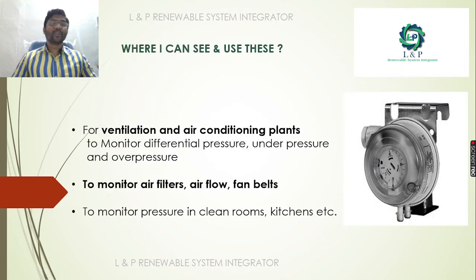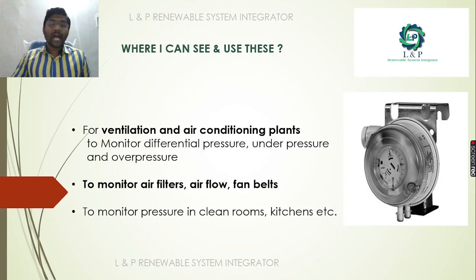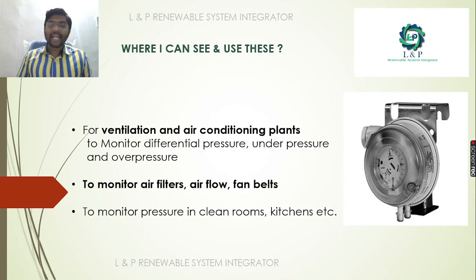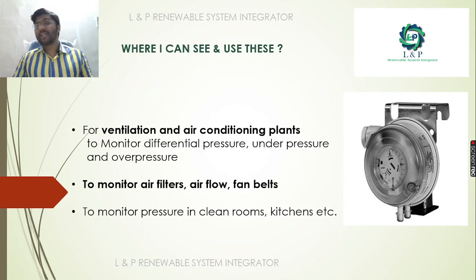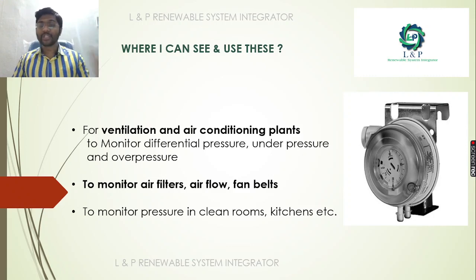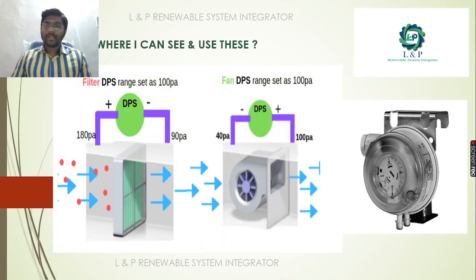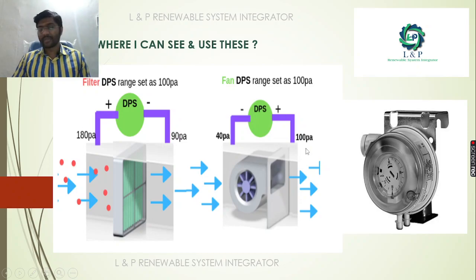This differential pressure switch is mostly used in heating, ventilation, and air conditioning systems. Most importantly, it is used to monitor filters — air filters. It is also used to monitor fan airflow and fan belts. Even in kitchens and clean rooms, we can use it to monitor pressure. It can be installed across filters and fans.